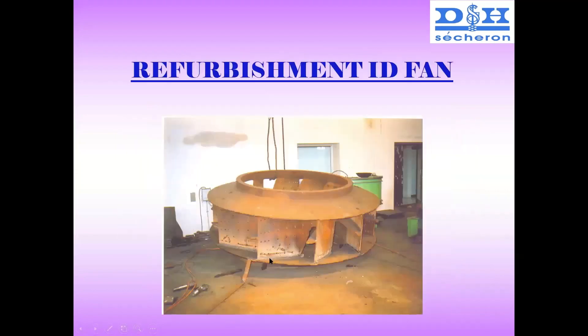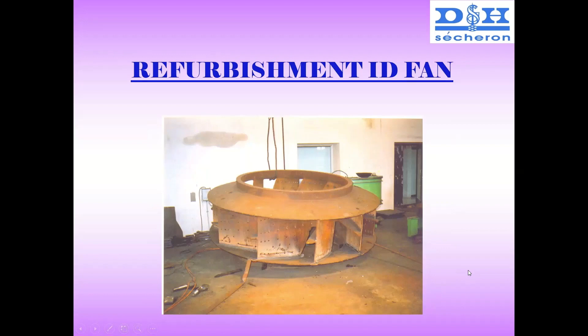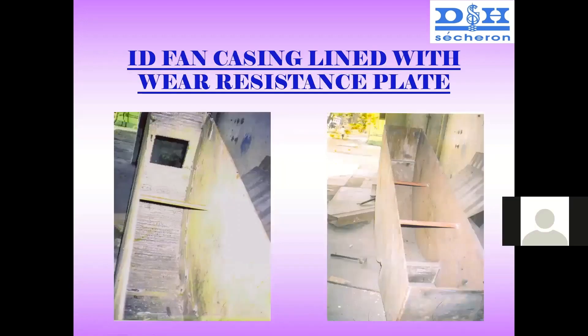In the boiler area, this is a typical ID fan. Sometimes customers have an ID fan where the vanes are broken — they will weld new plates. But the issue is that balancing must be done. If just hard facing the vanes, it is probably not necessary to balance since the hard facing deposit is not very high — just hard facing using a cross and checkered pattern. But if you put a wear plate on it, balancing will be required and installing it as-is will be dangerous. The ID fan casing also gets worn out — for small areas hard facing is done, for big areas a wear plate is sometimes used.